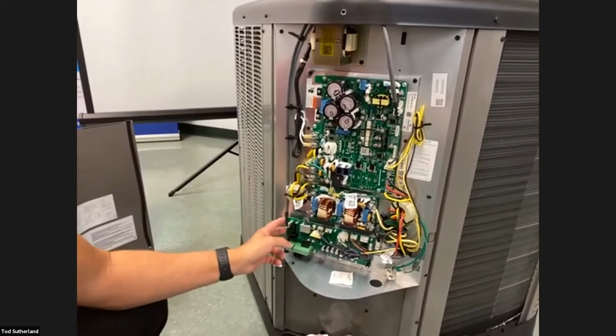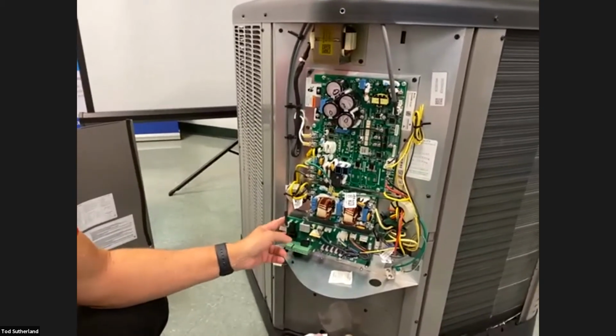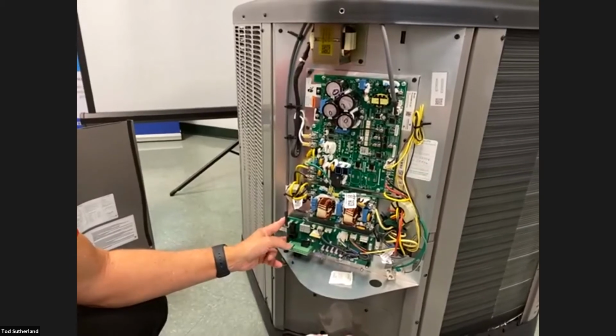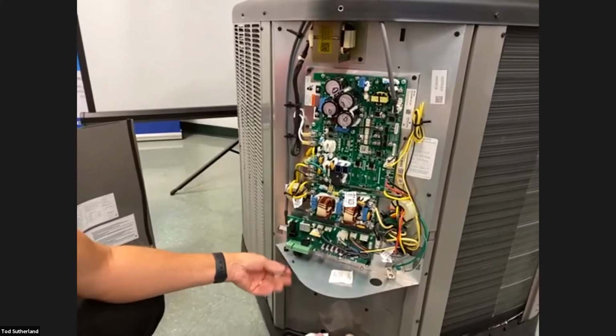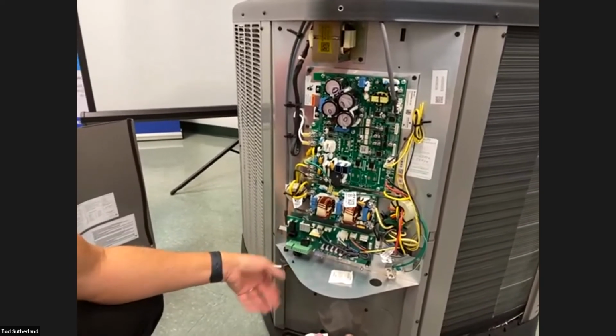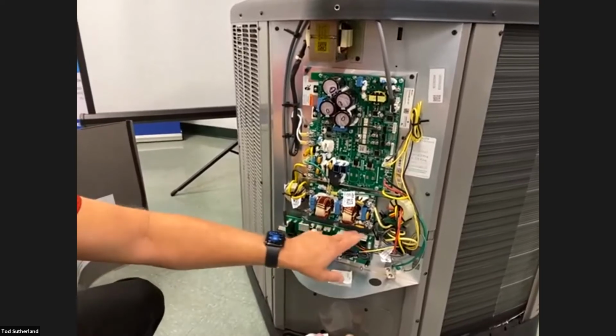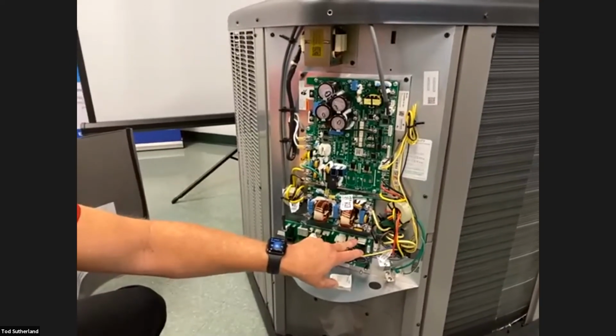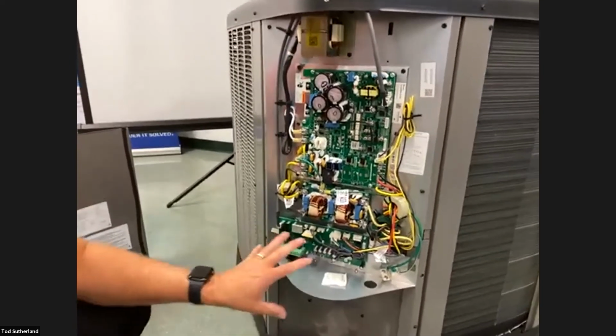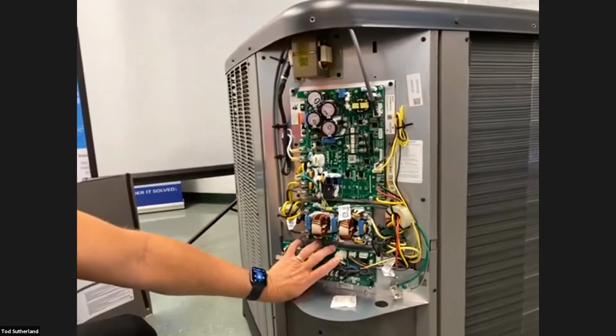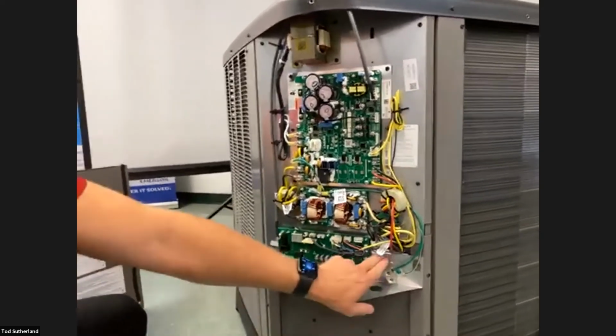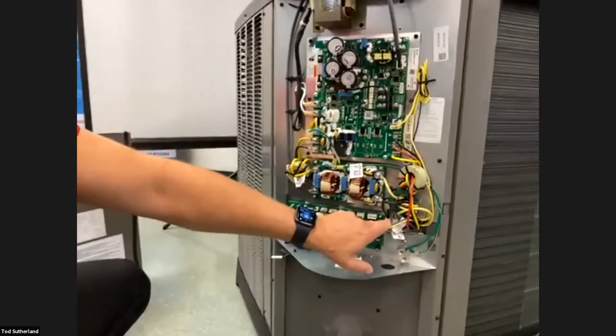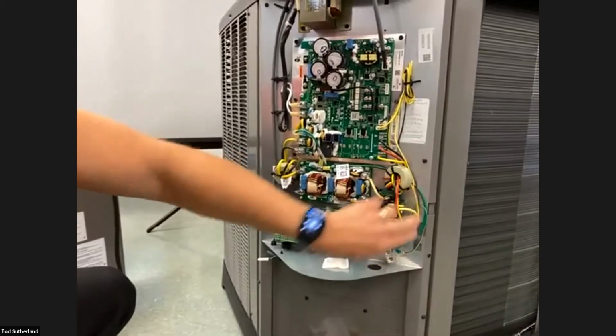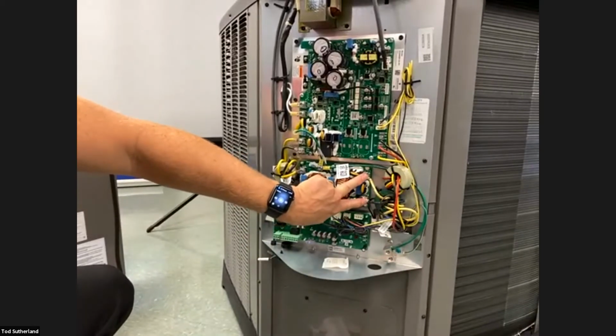This is what's called the VSODU board, the variable speed outdoor unit board, okay? And this is what your different thermistors will connect to. This is what your fan connects to. This is what your pressure transducers connect to, all into this board. From here, you've got your high voltage that comes in, and the high voltage goes through these ferrite rings and comes right into the filter board, okay?